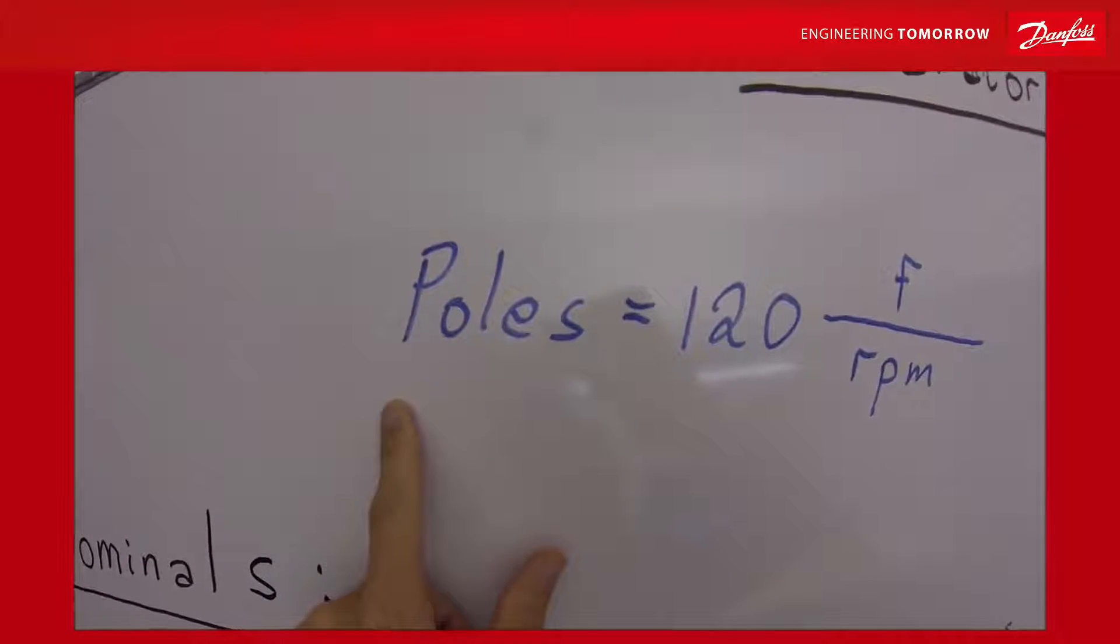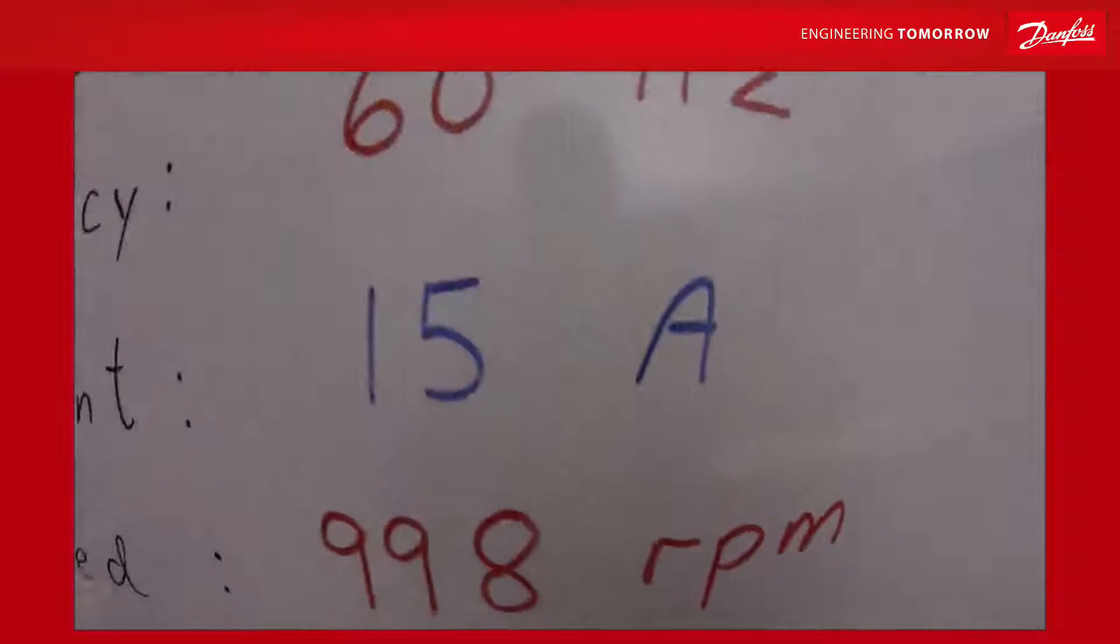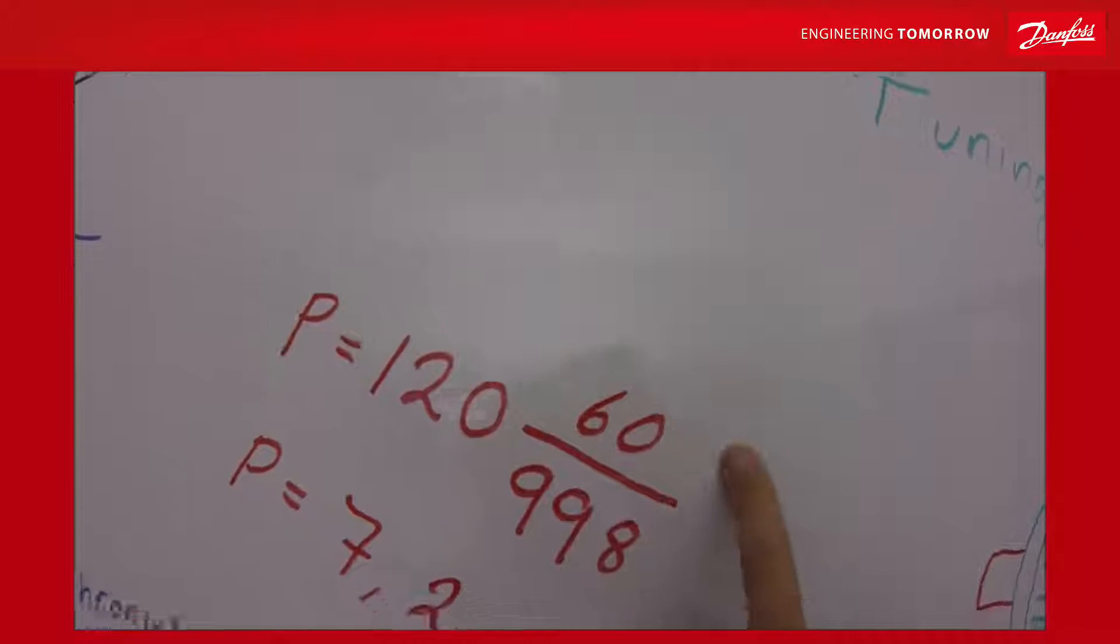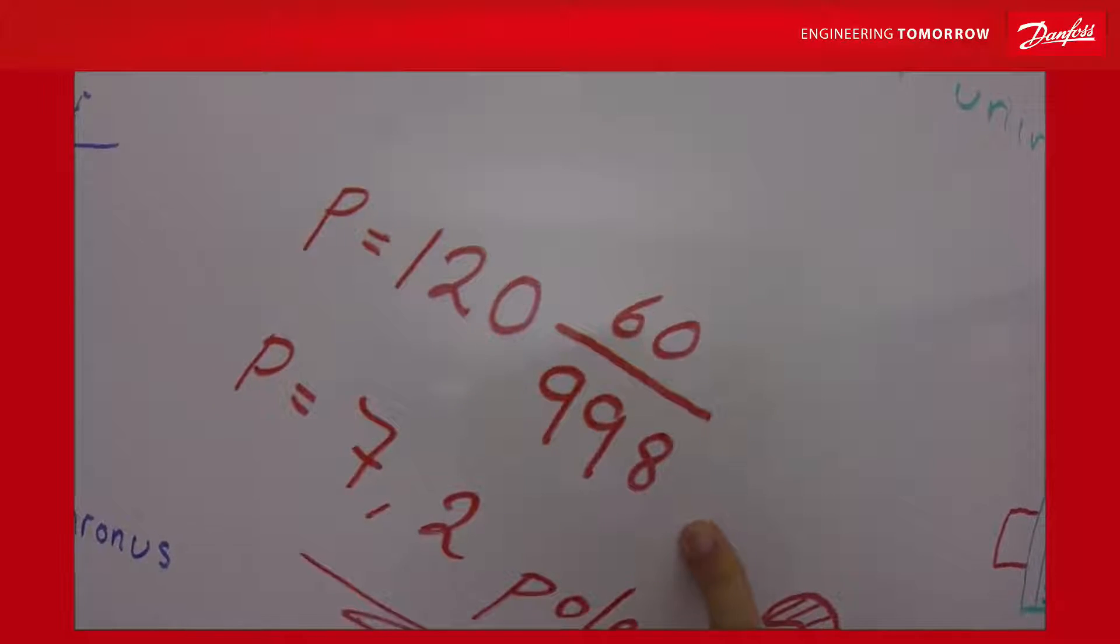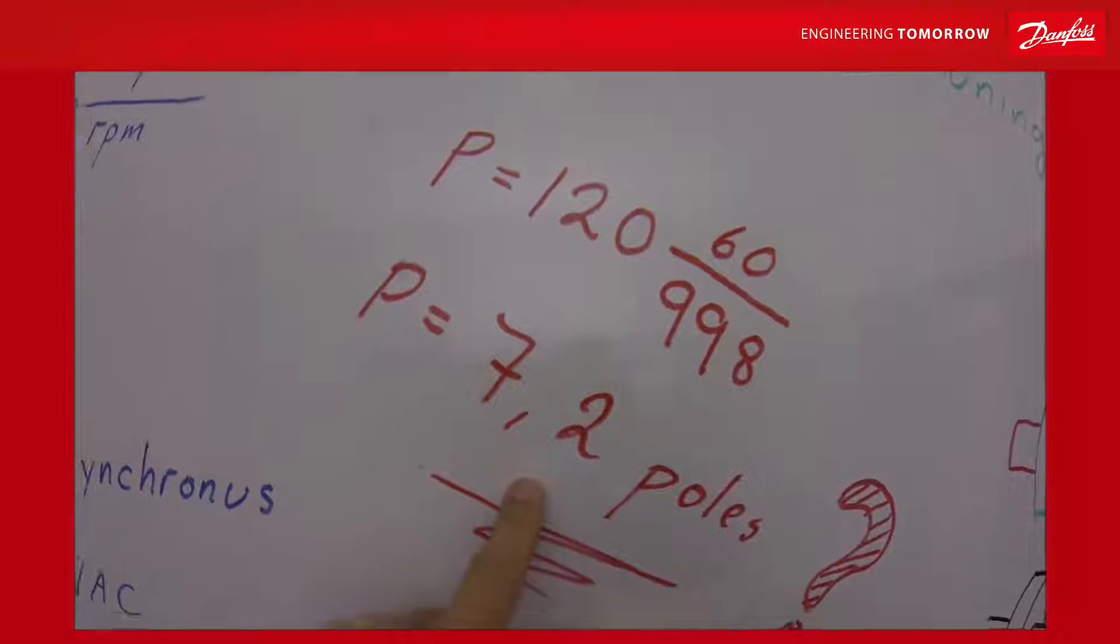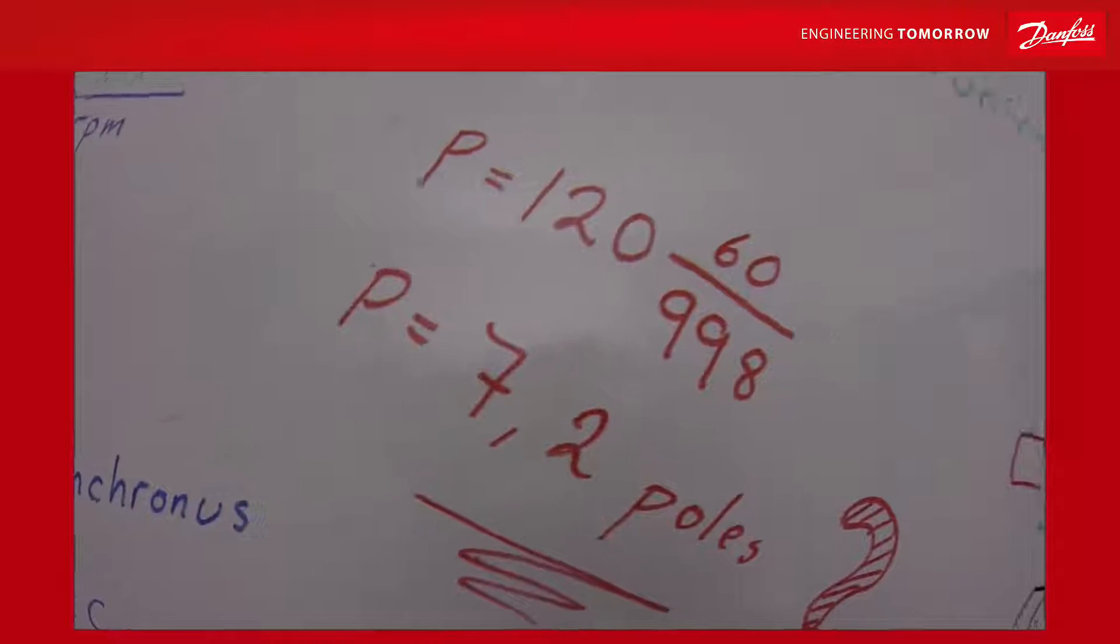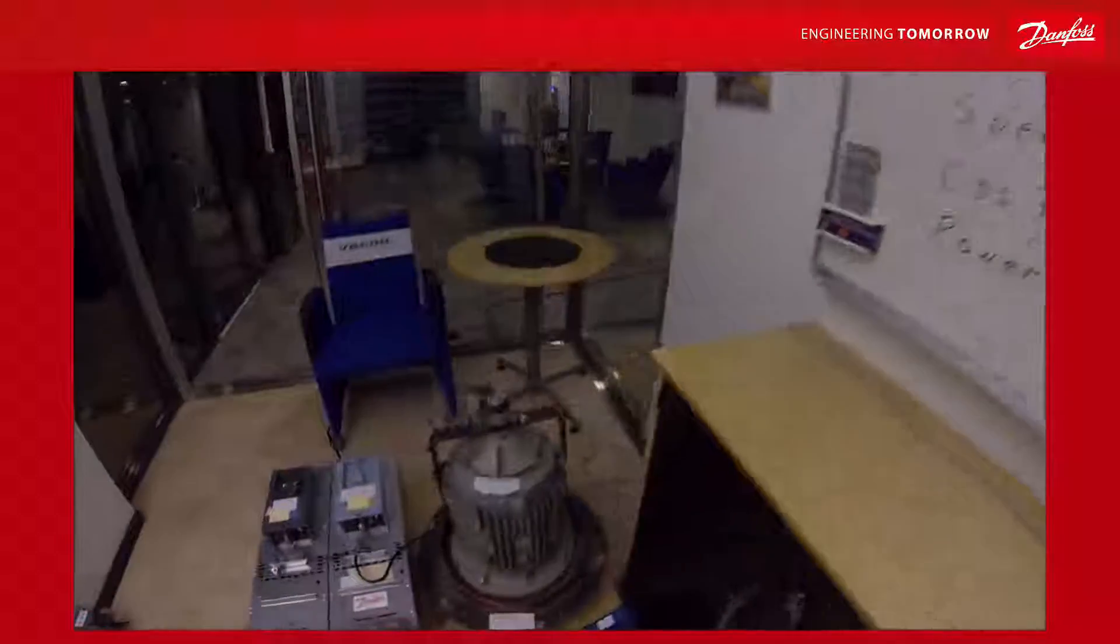The relation between the frequency and RPM will give the pole number. If I put these numbers into the equation something strange. 60 Hertz, 998 RPM. 7.2 poles cannot be right. It should be some number without decimals. So we can do a test to check what actually this motor produces.